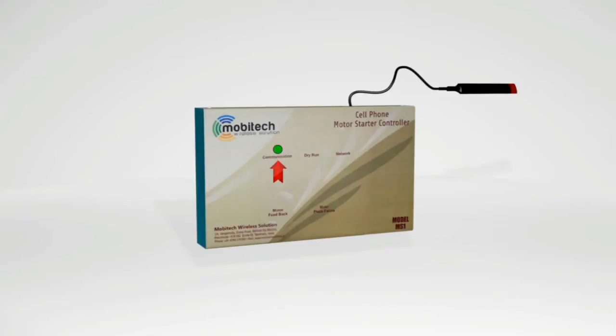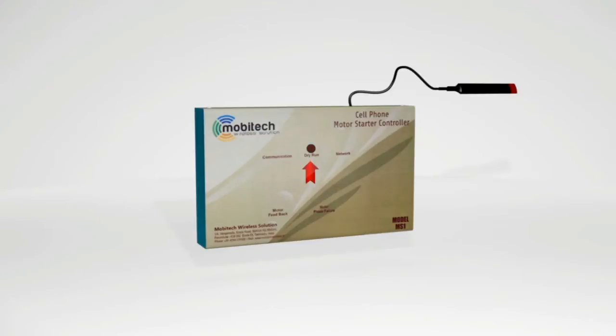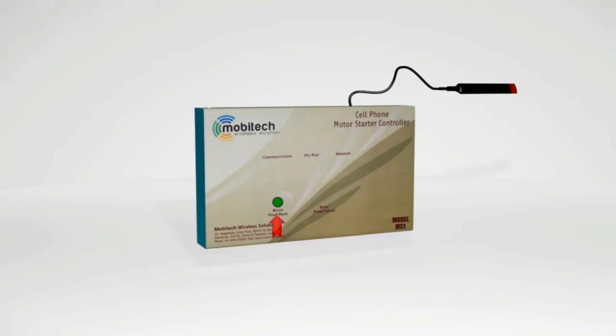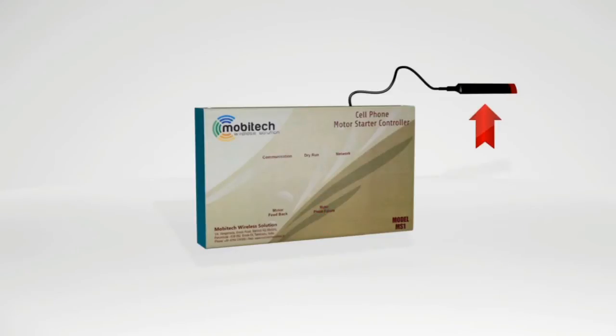The dry run or tank full LED glows if motor runs out of water in dry run mode or tank is full in level controller function. Network LED blinks in green color in two ways: every one second if not registered in network, or every five seconds if registered. Motor feedback LED glows green if motor is running. Phase failure LED glows red if phase fails, indicating phase imbalance and low voltage.